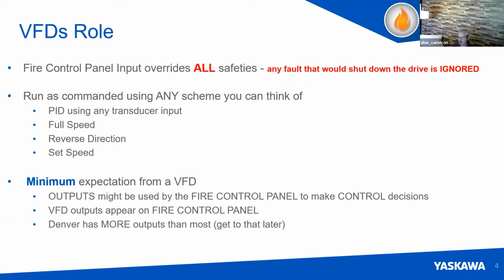When the drive receives a fire control input, which is programmed, there's a default input for it, we can set it to whatever you want. When that input is triggered, it ignores every single fault code that would normally shut down the drive, in the case of over current, over voltage, ground fault, whatever the fault would be. So that's how fire mode fits into the drive topology: there are no faults when you're in fire mode. When that input is triggered and set as the fire mode input, it's going to run to destruction.